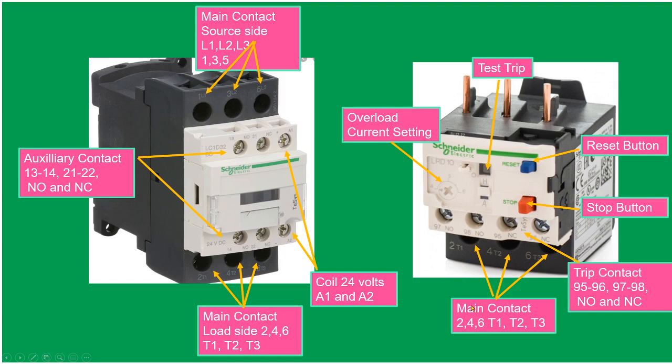On the other side, it's main contact two, four, six, T1, T2, T3. This is the load side. This three prong here is where we're going to connect from the load side of the magnetic contactor. Here on the other side, we also have trip contact: 95, 96, 97, and 98. 95, 96 is the normally closed.